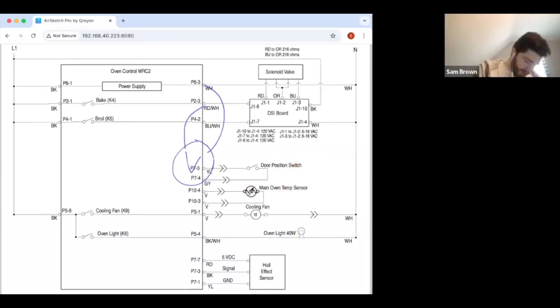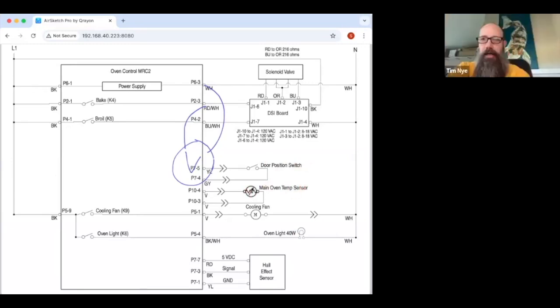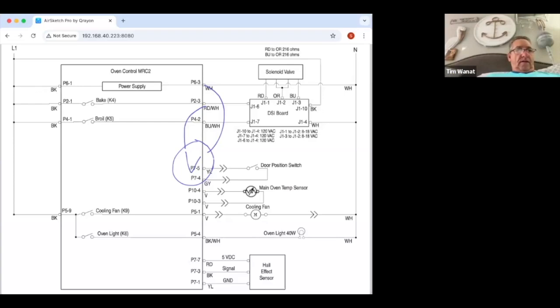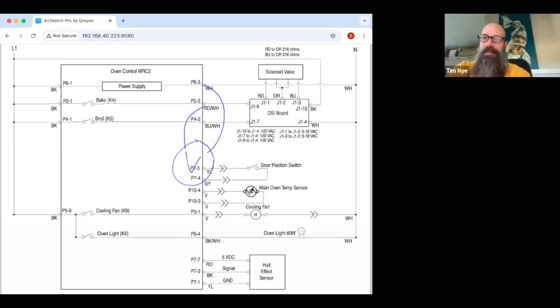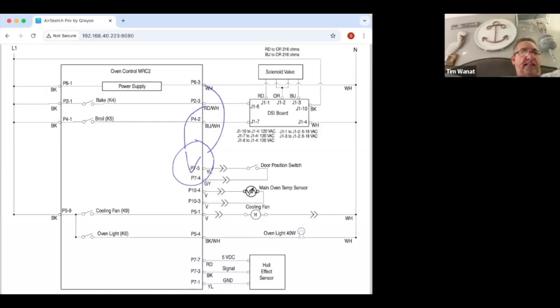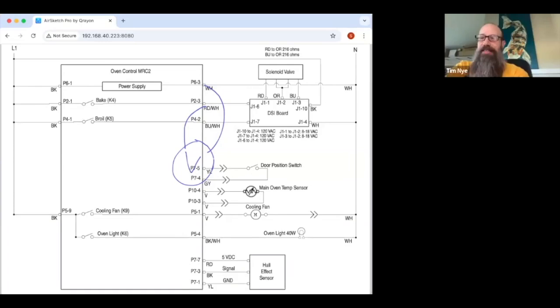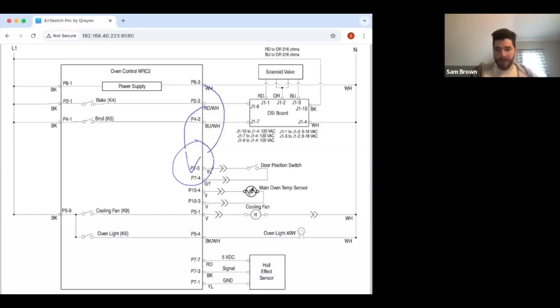There's no door switch here, just the temperature sensor. That logic on the board that reads the temperature sensor was probably the faulty part, because that's the part that tells it to open up. That's the only circuit, the only external source giving it information. Right, there's no other input to the board that could be lying to it, telling it not to run the burner.